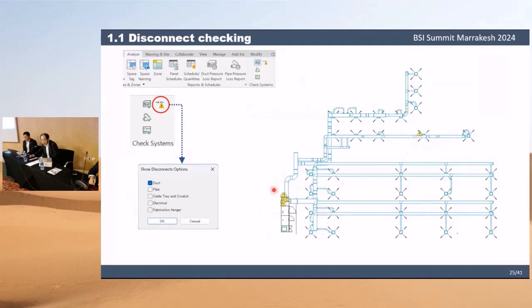We developed a tool to visualize the 3D model and the pressure loss in the duct path. The level 1 critical path is highlighted. The pressure loss will be illustrated on the right side. The total pressure loss can be used to select the suitable fan for an air handling unit system. At the diverging fitting here, we can get a level 2 critical path, with the pressure loss here about 62 pascals. At the level 1 path, the pressure at the fitting is 99 pascals. This means there should be a damper set on this path.